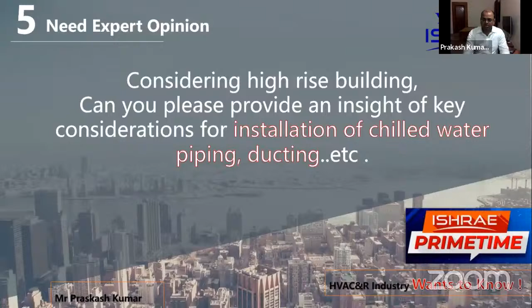I think these are the key considerations for designing chilled water piping and ducting. Keep the ducting as minimal as possible, and if it's possible to avoid it, then avoid it. For smaller spaces, you can use FCUs, fan coil units, instead of AHUs. If you can do that, it's better. If you cannot, then use ducting, but keep the size of the duct as minimum as possible.